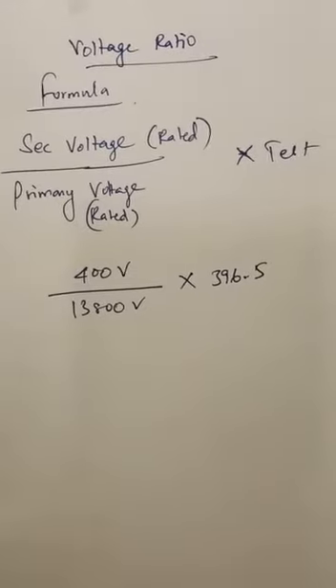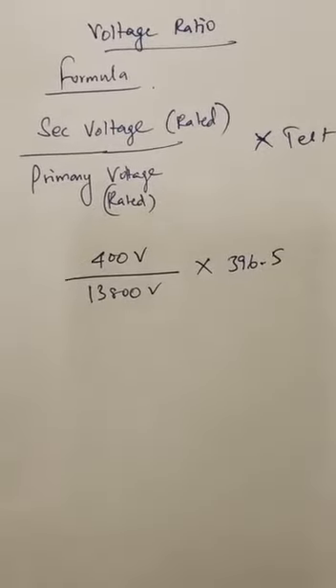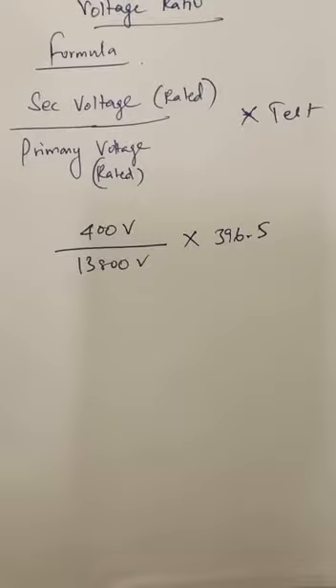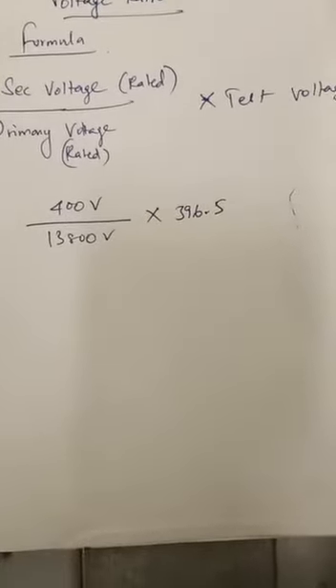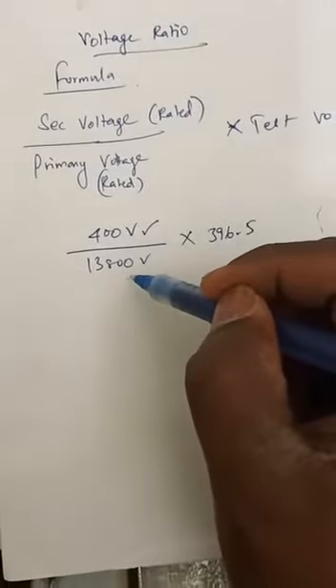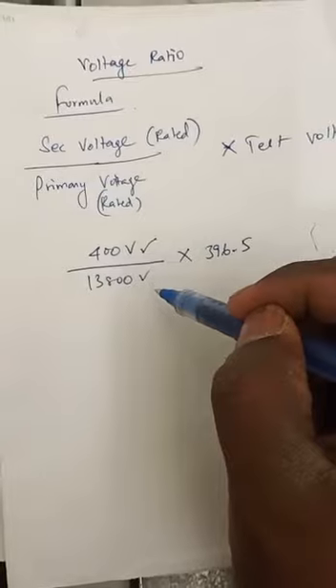This is the formula for voltage ratio: secondary voltage divided by primary voltage and multiply by test voltage. So our secondary voltage is 400 volt and 13.8 kV is the primary volt and our test voltage is 396.5.